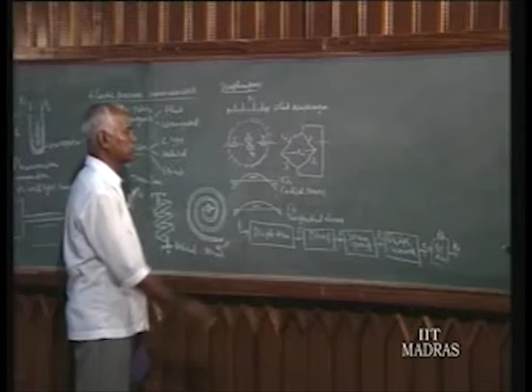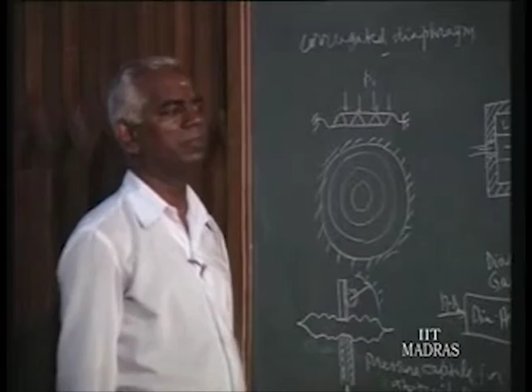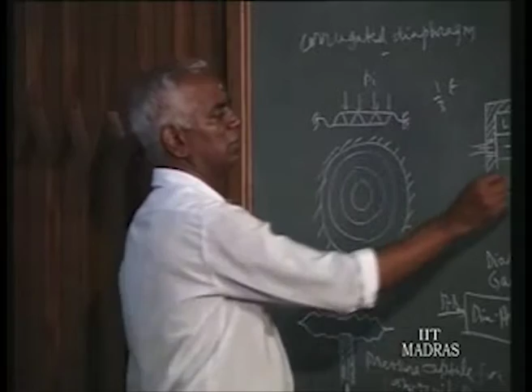The next type is corrugated diaphragms. The disadvantage of the flat diaphragm is that the maximum deformation of a flat diaphragm can be 1/3 the thickness of the diaphragm. So this is one diaphragm where T is the thickness of the diaphragm. 1/3 the thickness alone it can deform. More than that, the deformation is non-linear to pressure applied. So to overcome this drawback, people go for the corrugated diaphragm.